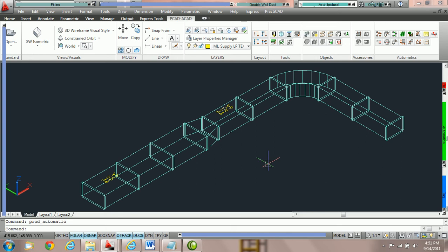The first change we're going to make is an elevation change. To change the elevation of a duct line, or to move it up a specific amount as a whole, other than using the AutoCAD move commands, we can just simply click on the first fitting we'd like to change and then change the elevation of that fitting. If we move that fitting up 2 feet and all of the other ducts are attached, the entire system will move up 2 feet. We do not need to highlight all of the ducts, just the first one on the change.